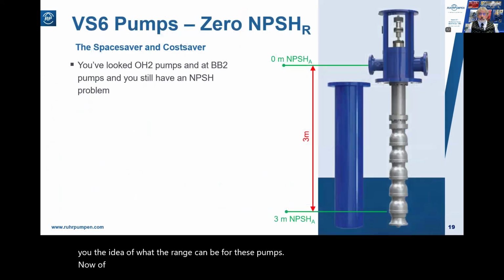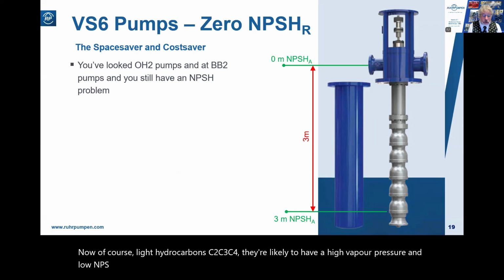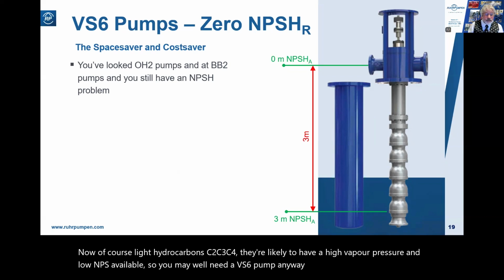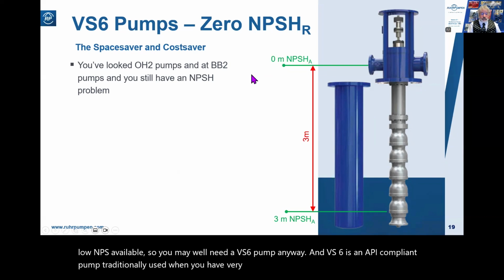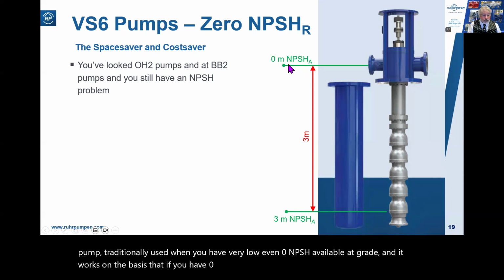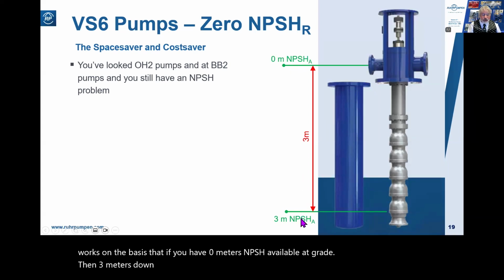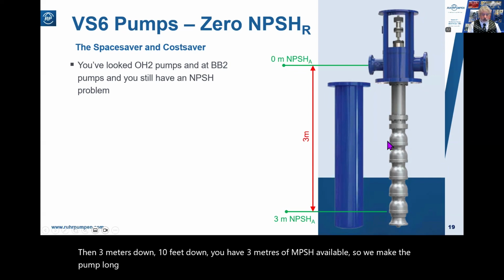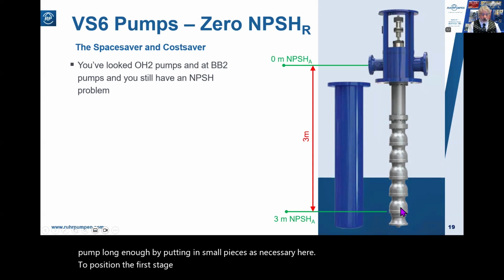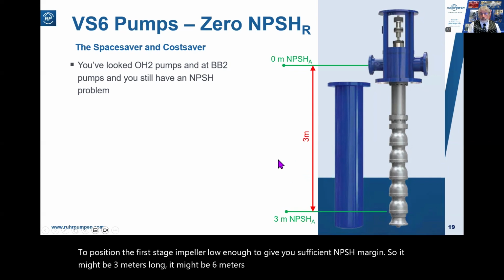Now, of course, light hydrocarbons, C2, C3, C4, are likely to have a high vapor pressure and low NPSH available. So you may well need a VS6 pump anyway, and VS6 is an API compliant pump. Traditionally used when you have very low, even zero NPSH available at grade. It works on the basis that if you have 0 meters NPSH available at grade, then 3 meters down, 10 feet down, you have 3 meters of NPSH available. So we make the pump long enough by putting in spool pieces as necessary to position the first stage impeller low enough to give you sufficient NPSH margin. So it might be 3 meters long, it might be 6 meters long, it could be 9 meters long.